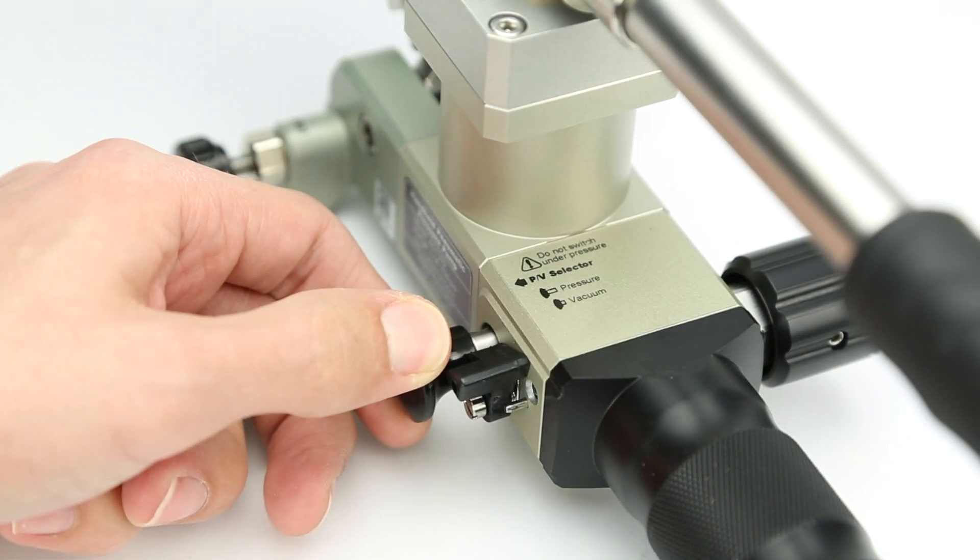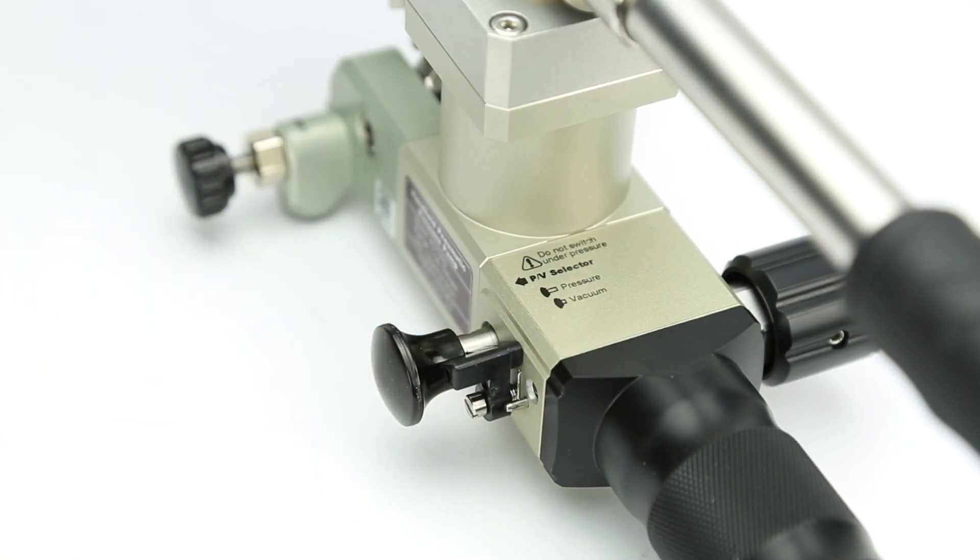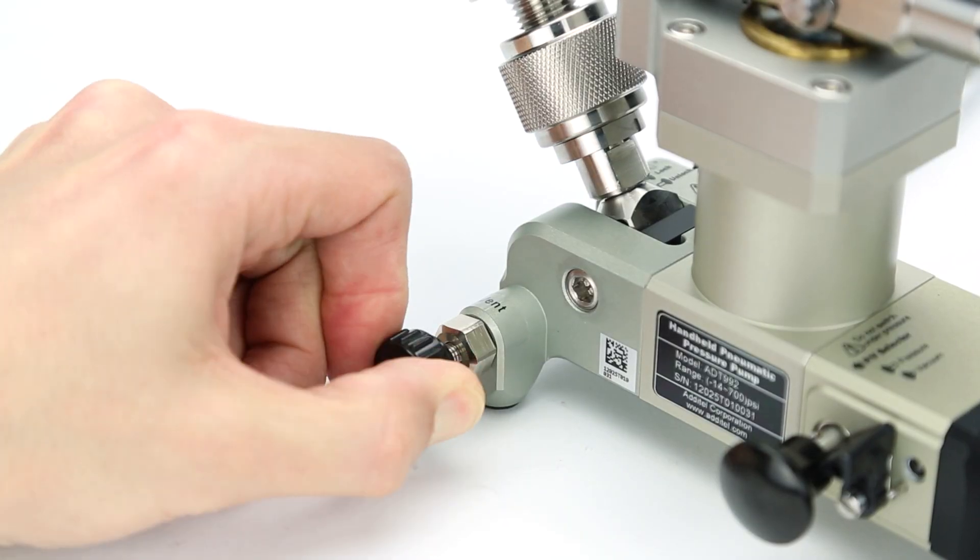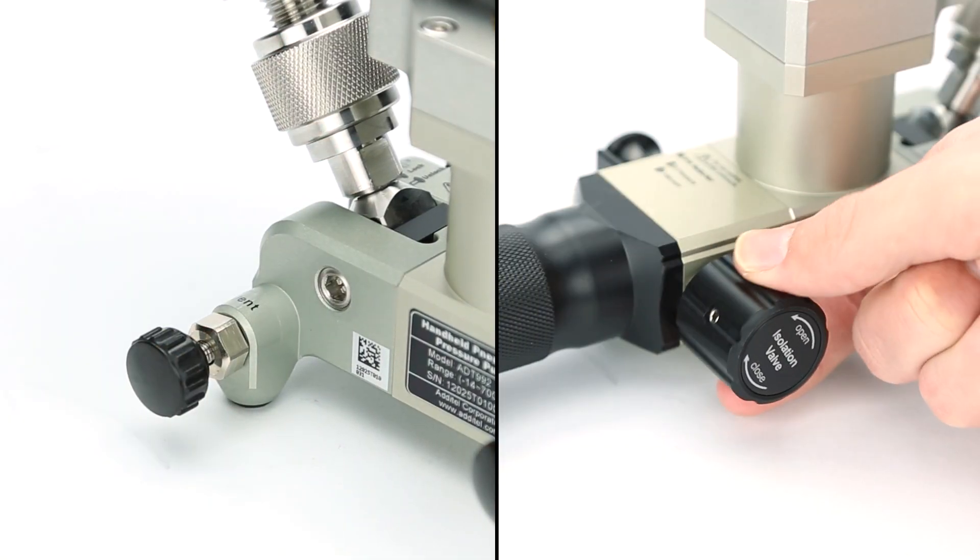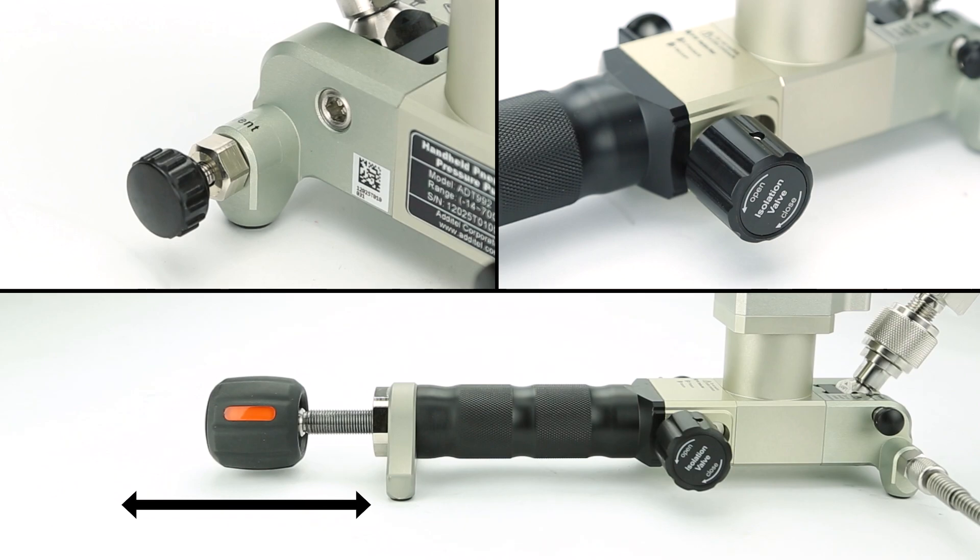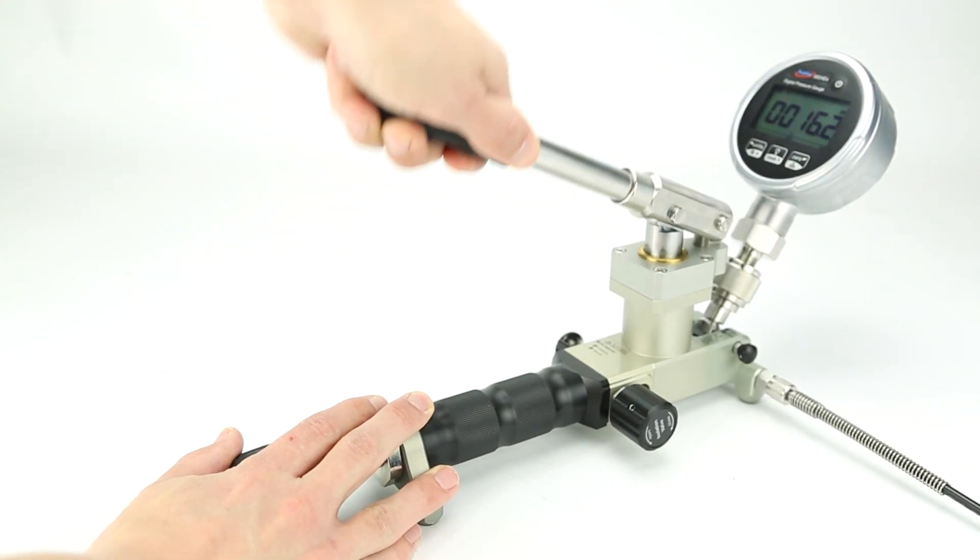Before pressurization, choose whether you want pressure or vacuum using the selector on the left side of the pump. Ensure the vent is closed, the isolation valve is open, and the fine adjust knob has room to operate in either direction before generating pressure with the main lever arm.